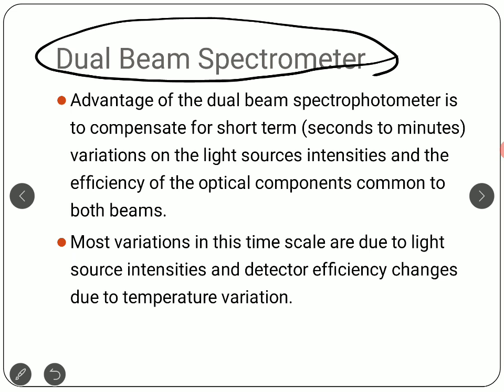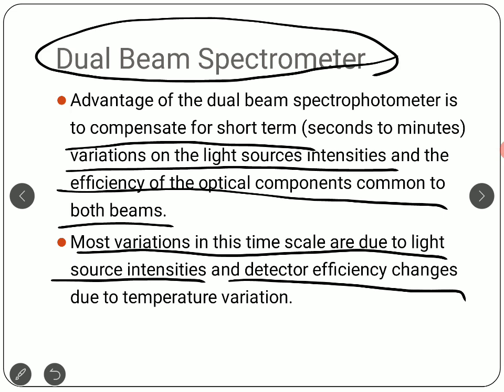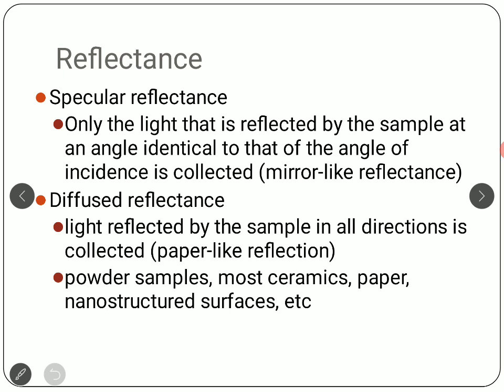The dual beam spectrometer has two beams and offers significant advantages. It compensates for short-term variations in light source intensity over the path from source to sample, and accounts for efficiency changes in optical components common to both beams. Most variations on this timescale are due to light source intensity and detector efficiency changes caused by temperature variation, so temperature is also an important factor to consider during measurements.